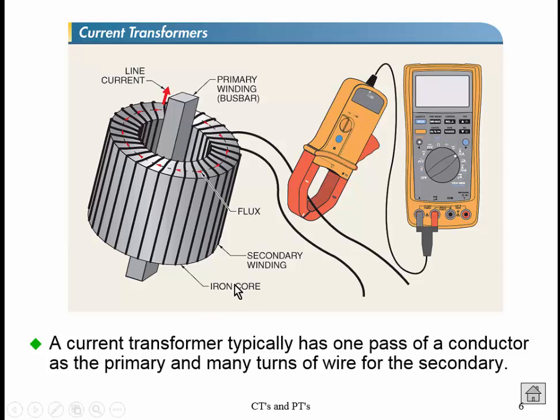So here's a little picture of a kind of a mock-up of a CT. Here would be the main power going through the middle, and we call that the primary winding. And then the secondary is really just these wraps around this core. And you'd have to go around and count those, but there might be, let's say that's 20 wraps. Well, then that would be 100 to 5 CT. If we have 100 amps flowing through the primary, we'll get 5 amps on the secondary.